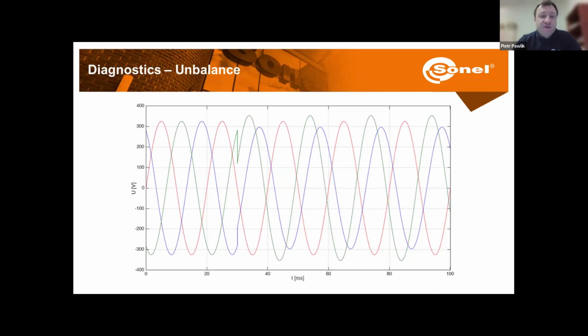The next thing that we would like to check will be unbalance. So if we have a three-phase charger, well, this problem should not exist. But when we use multiple single-phase chargers with higher power outputs, this can result in unbalance of currents and voltages. Even if the chargers are installed in different phases, it may not be possible to force all of them to work at the same time at the same load.